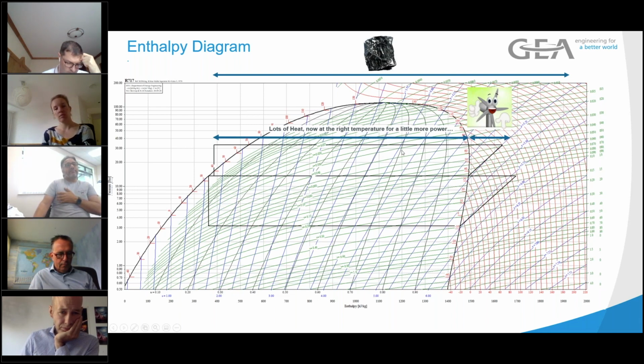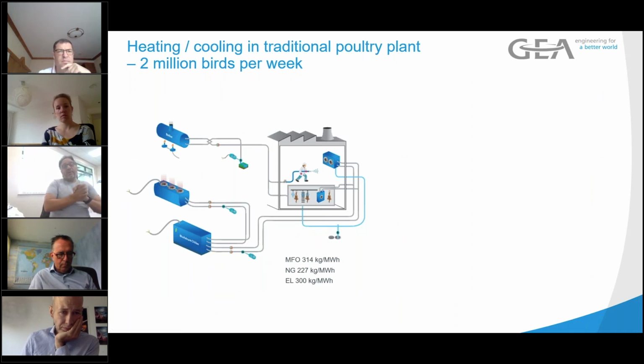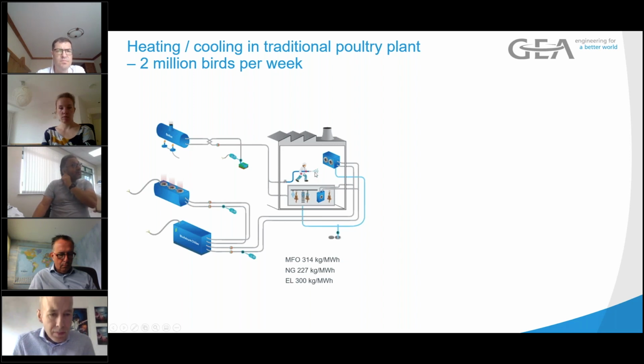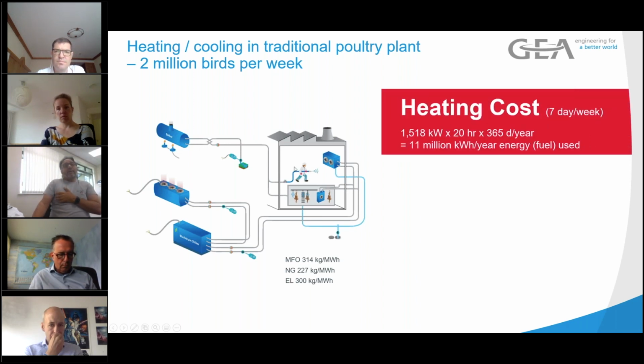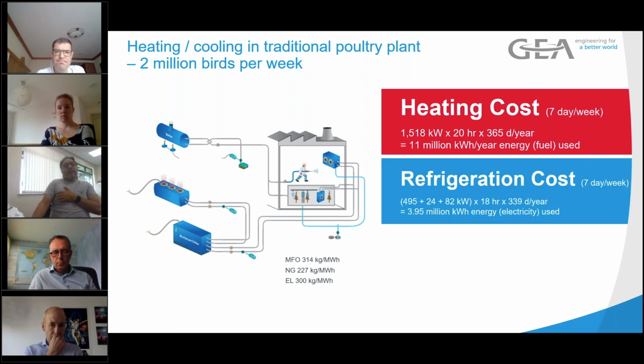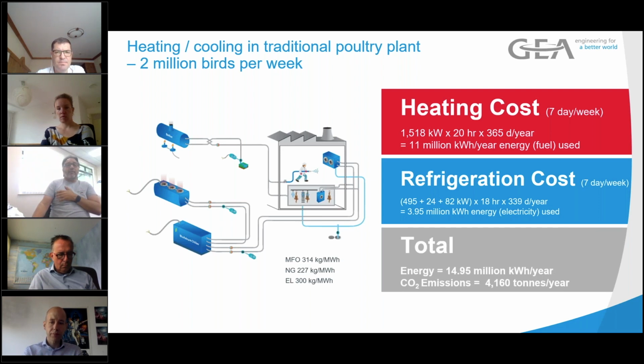Some examples of this, again, if we go back to one of our poultry plants that we've done, you have the boiler chugging away, producing hot water. These guys use a lot of hot water at night time in a refrigerated environment. The factory's a fridge, basically. It's also sprayed onto the birds at around 52 degrees. And then the birds are cooled down and go into cold stores, etc. If we map the amount of energy that we're putting in, that's equivalent to 11 million kilowatt hours for heating, 3.9 million kilowatt hours for power for the refrigeration side. So combined, nigh on 15 million kilowatt hours per year and 4,000 tons of CO2.